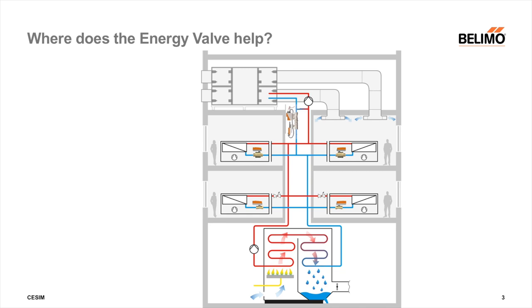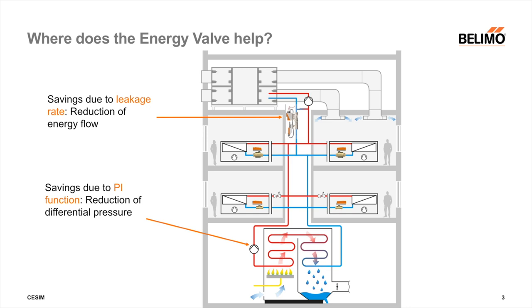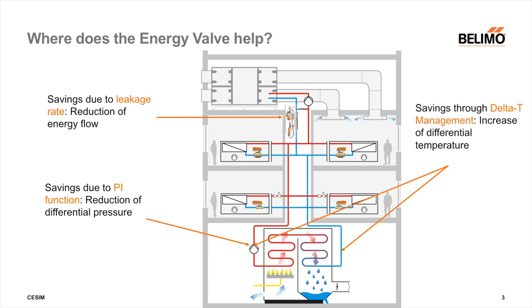Where does the energy valve help? The energy valve helps in three places in a building: reduction of the energy flow through a better leakage rate; with hydraulic pressure independence, the pump performance can be reduced by reducing the differential pressure at the pump; and increasing the differential temperature in a condensing boiler improves efficiency. I would like to briefly address these three points.